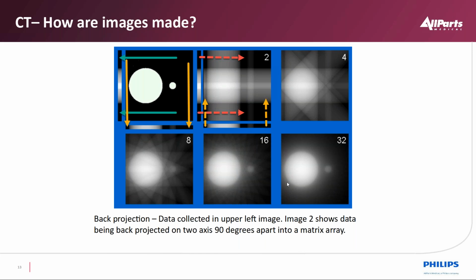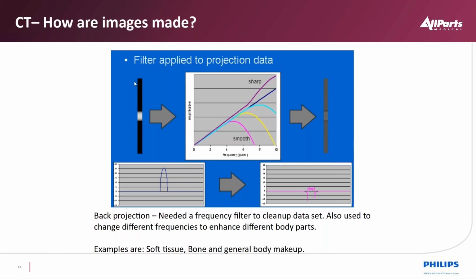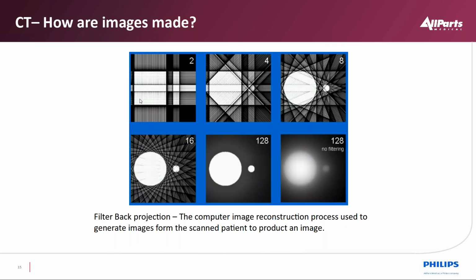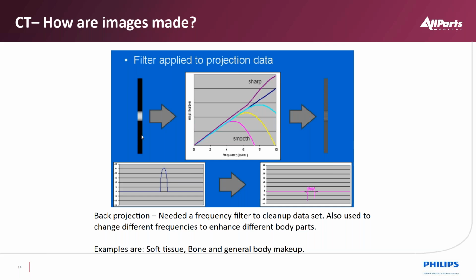So in the process itself, when we do CT reconstruction, we have what we call inherent artifacts that have to be cleaned up. So in doing that, we would then add a filter. All scans are done with a filter applied. Think of this as a frequency response filter, where the data collected on the left side would represent this little spike in blue here on the left side.